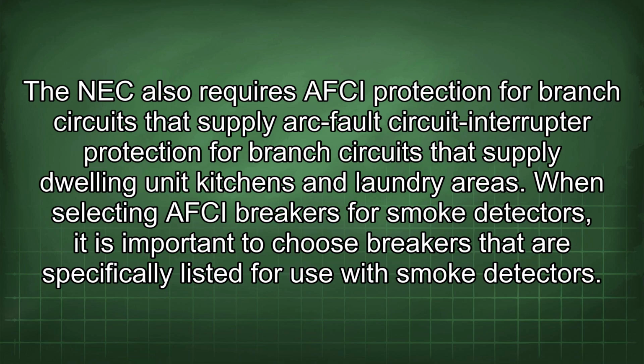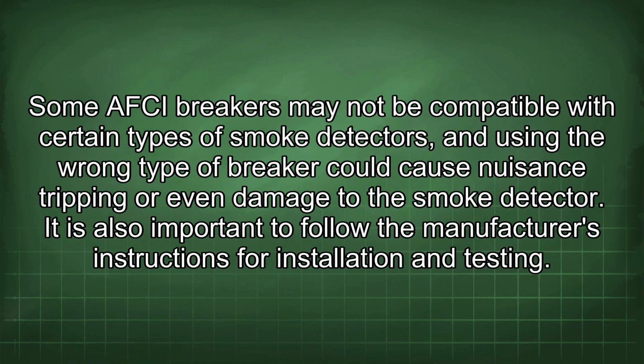When selecting AFCI breakers for smoke detectors, it is important to choose breakers that are specifically listed for use with smoke detectors. Some AFCI breakers may not be compatible with certain types of smoke detectors, and using the wrong type of breaker could cause nuisance tripping or even damage to the smoke detector.